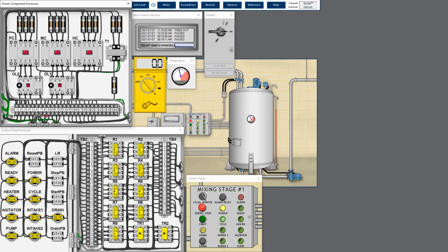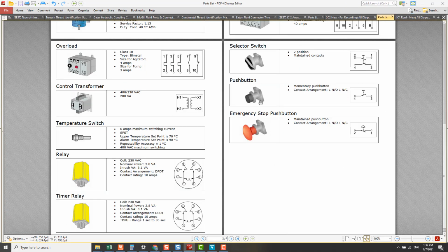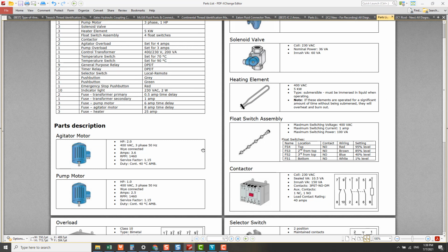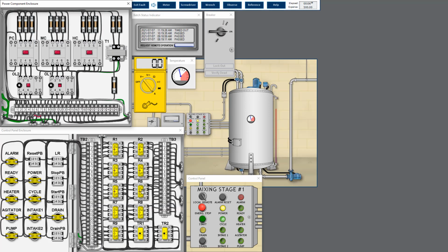Now it reaches 70 degrees, the pump is going to run soon. Oh, there's no current here, there's current here, there's current here. Okay, so the current 14.8 ampere is very high. This one can be considered overload current. The full load current is supposed to be around 2.3 something. By looking at the technical spec, the pump motor should run at 2.5 full load ampere, FLA, that means full load current. So now you get 14.8, it's an overload current.